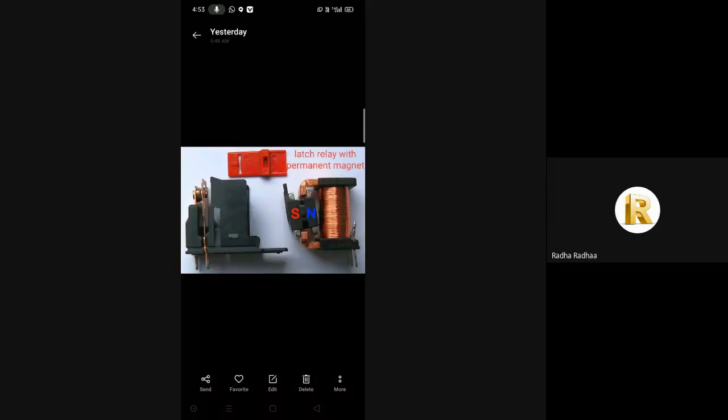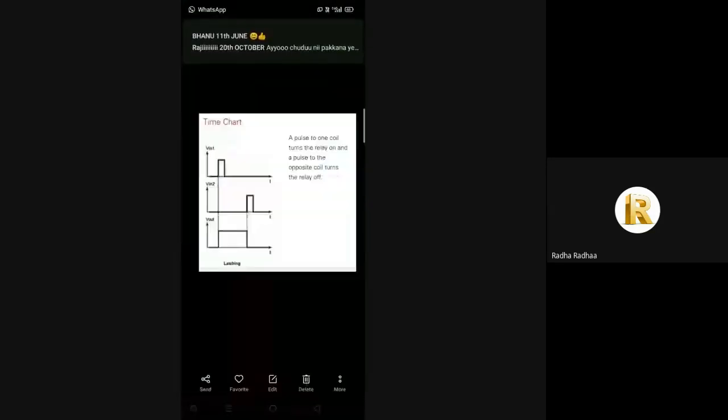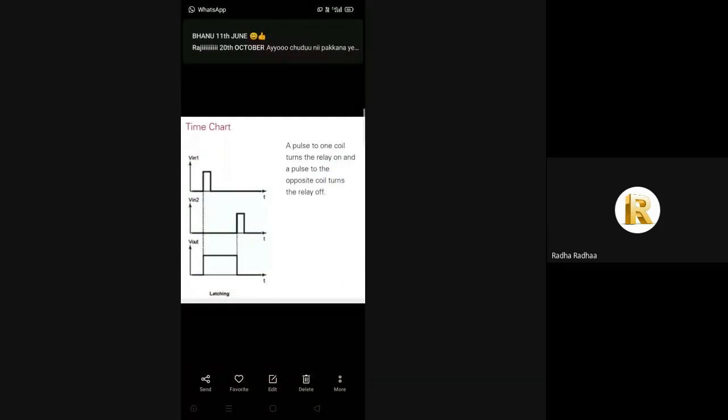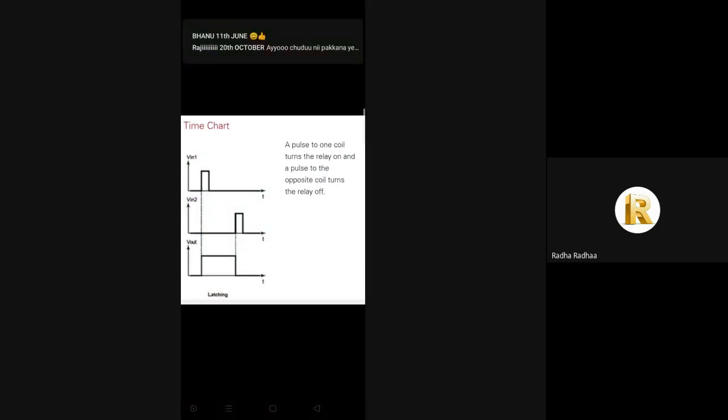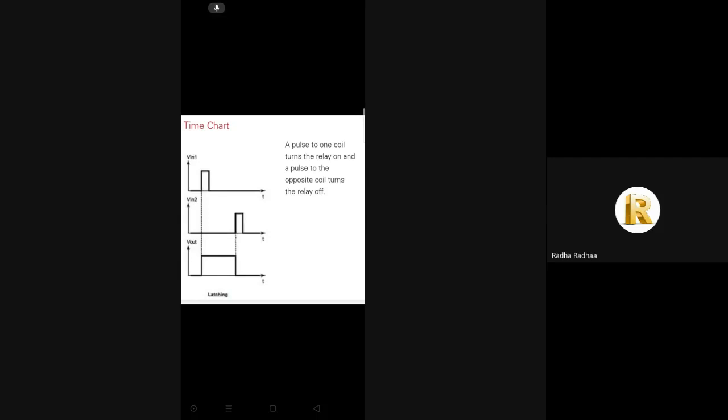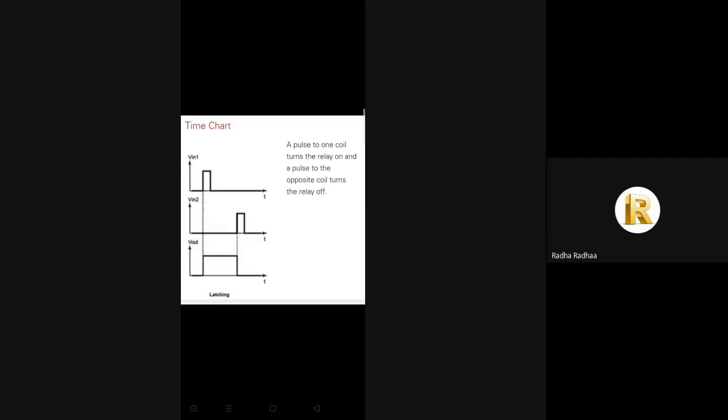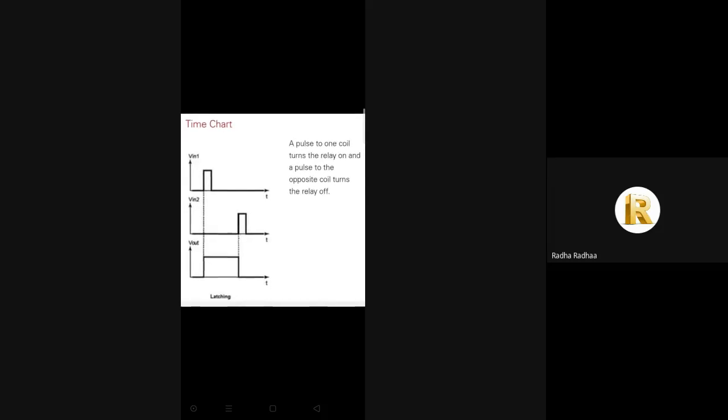It maintains its position after the actuating switch has been released, so it performs basic memory functions. In the time chart of a latching circuit, the pulse to one coil turns the relay on and the pulse to the opposite coil turns the relay off.